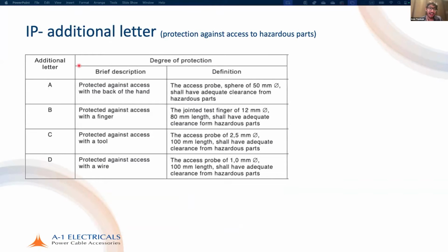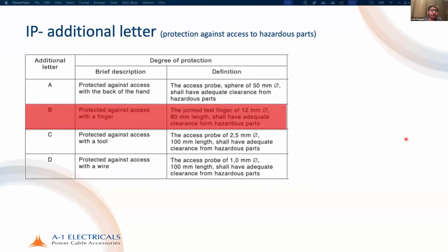There are also additional letters when we have IP. For example, the additional letter may be A, B, C, or D. So for example IPXXB or IPXXD, like we spoke about. These are used in some specific situations. For example, the first situation is if the degree of protection against access to hazardous live parts is higher than indicated by the first characteristic numeral for ingress of solid foreign objects. So you provide a greater degree of protection against access to hazardous parts than you provide for ingress of solid foreign bodies, then you can use this. Or if there is no protection against ingress of solid foreign bodies, or it's not specified, then it is there. So IPXXB means that it is not declared for protection against solid foreign bodies, but it is declared for protection against access with the finger. IPXXD means it is not declared for protection against solid foreign bodies or water, as a matter of fact, but it is there for protection against access by a wire.